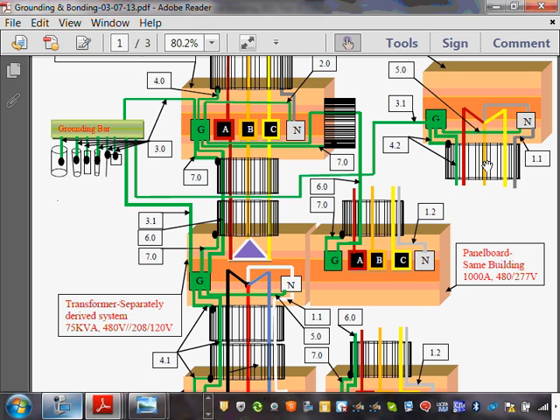So you're saying if you have a grounded system, you always need a grounded system transformer, generator. If you are to utilize the grounded voltage, but if you're feeding three-phase only here, like Jeff said, we're just feeding three-phase pumps only, and our auto transfer switch is tied to a power panel that has three-phase only. We're not tying anything that's phase to neutral. Then you don't have to pull the neutral. But if anywhere in your normal system you're running a neutral, yeah, a generator would be. Yes, only if the generator is utilized, meaning you're tying things to the generator.